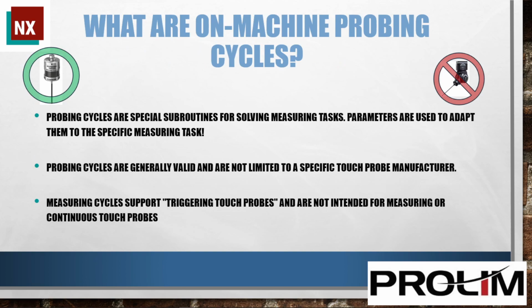So what are OnMachine probing cycles? Probing cycles are special subroutines for solving measuring tasks. Parameters are used to adapt them to the specific measuring task. Probing cycles are generally valid and are not limited to a specific touch probe manufacturer. Measuring cycles support triggering touch probes and are not intended for measuring or continuous touch probes.